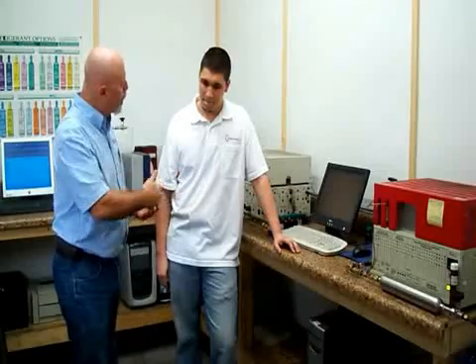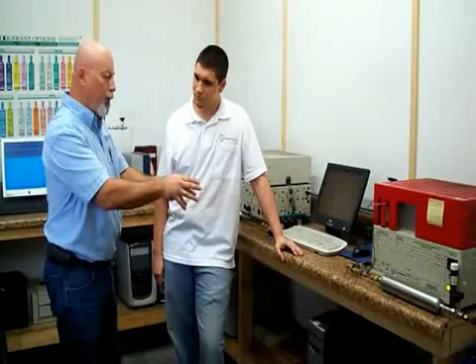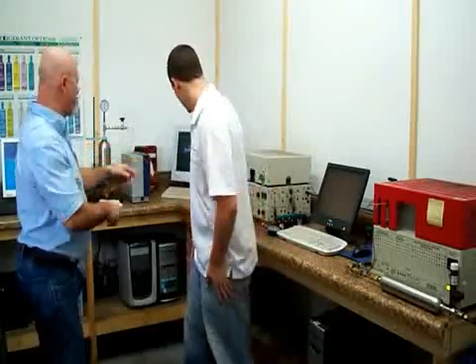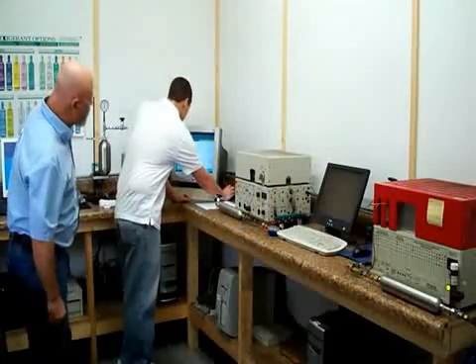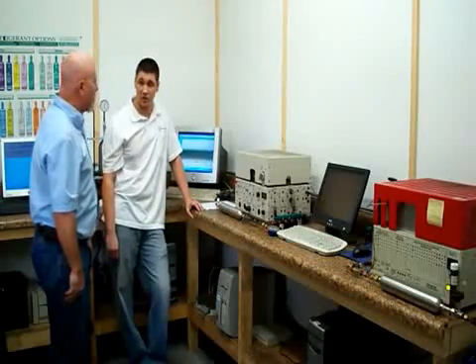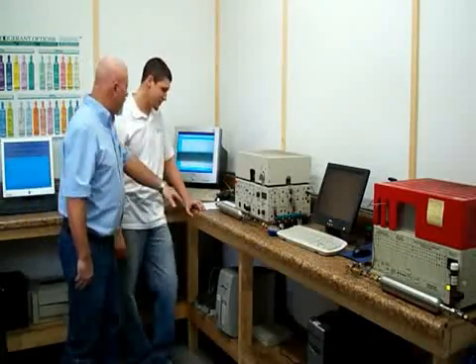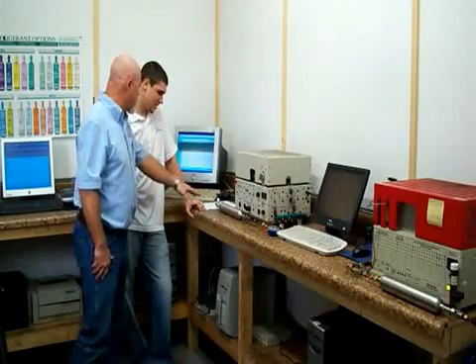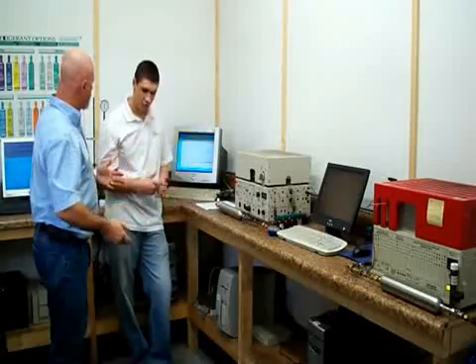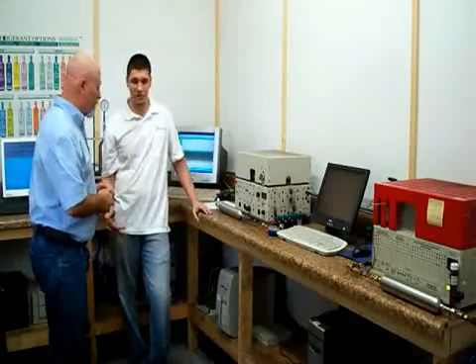What do you do with that printout? We return it to our secretary and attach it to a folder along with whatever Trey checked it in with. This machine is for low pressure refrigerants — what does the other SRI machine do? Moving over to this other SRI machine — this one tells us the air content in all of our necessarily certified tanks, which is our EPA certification. We use this one primarily for high pressure gases, which would include R22, R134, R410. It gives everybody a key indicator of the air on top of the cylinders for everything we run at CRS.